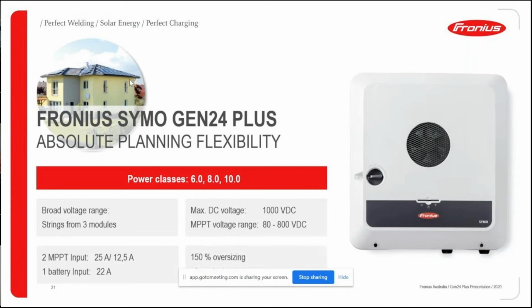And where it says here 150% oversizing, that's approved by Fronius and guaranteed by Fronius, that you can oversize the PV array 50% over the AC rating of the Gen24. Now, obviously, in Australia, we've got the CEC rules around 33% oversizing. However, if you have a battery added to the system, you're not restricted to that 33% oversizing. You can oversize up to 150%. So that means that, yeah, you can have larger PV arrays on the inverters.